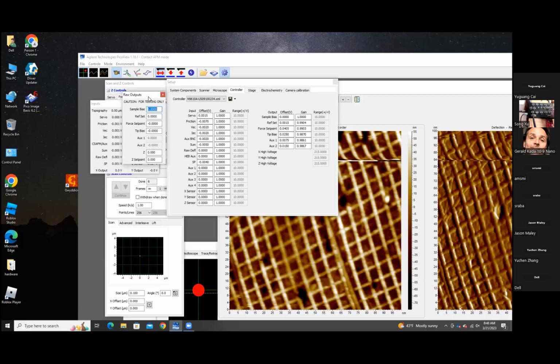Okay, I'm going to look at the sample bias out. Let me go not to the 1,000 volt range, give it the 20 volt range in case we get it high. Yeah, the reading is fluctuating a little bit. Let me push it hard a little bit on my fingers. Negative 0.12. So again, you're going to put the opposite value into the sample bias offset and then measure it again. Now, when you're measuring your outputs, keep in mind that the offset that you put into the software is going to deviate a little bit from your multimeter, and you're going to have to fine tune it and dial it down to the specific 0 volt.